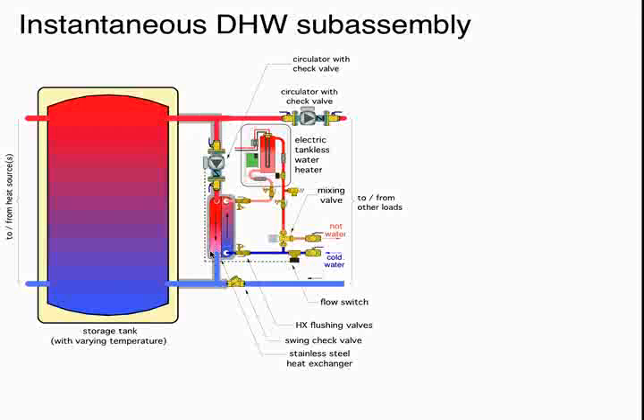So imagine we've got this mounted close to the sidewall of the tank. It's only going to be a couple seconds before we have hot water from the upper portion of the tank passing down through the braze plate heat exchanger and back in the tank. And if you've worked with braze plate heat exchangers, you know they have a very fast response time. They have very high surface area to volume ratios. So again, a second or two will be a typical response time on those. So within maybe 4 to 5 seconds, we'll have heated water coming out of the secondary side of the heat exchanger. How hot will it be?